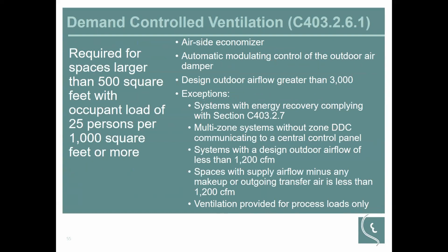Now, this could be done via an airside economizer, automatic modulating control, or design outdoor airflow higher than 3,000 CFM, as well as there are some exceptions to this. While demand-controlled ventilation in the past has been much more complex, there are now more and more thermostats that have demand-controlled ventilation capability built into them. That can be useful if you have a building that has, say, a single rooftop unit. With these new thermostats, you can now provide demand-controlled ventilation for these single rooftop units at a much more reasonable cost than it used to be available at.